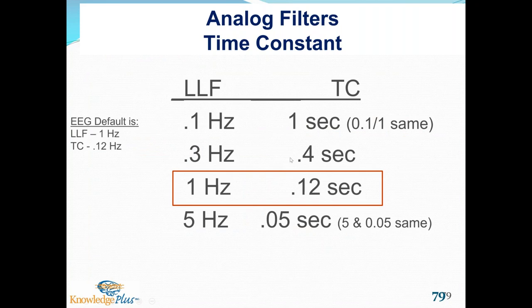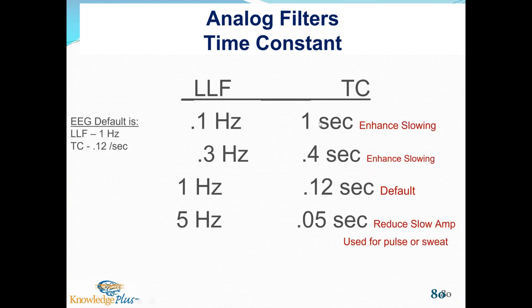Now, it's really important, not just for a test situation, but also as you move from lab to lab and work on different equipment that may have low filter, may have time constant. The default setting for low filter is 1 hertz. The default setting for time constant is 0.12 seconds. If I wanted to enhance slow activity on the low filter, I would choose 0.1 hertz. For time constant, it would be 1 second. For low filter, if I wanted to get rid of sweating or pulse, I would use a 5 hertz low filter. For time constant, I would use 0.05 seconds.